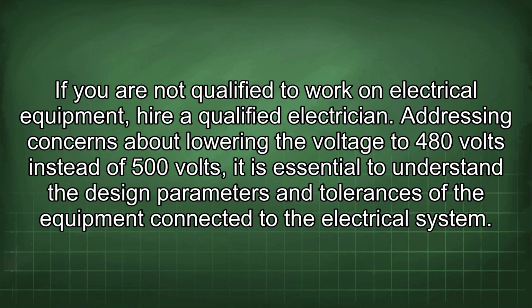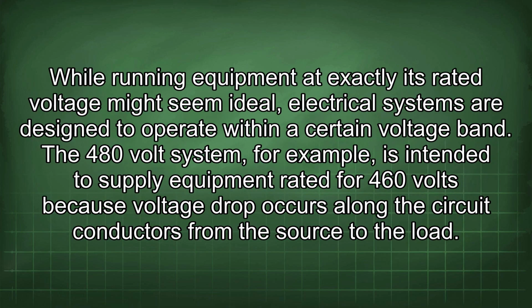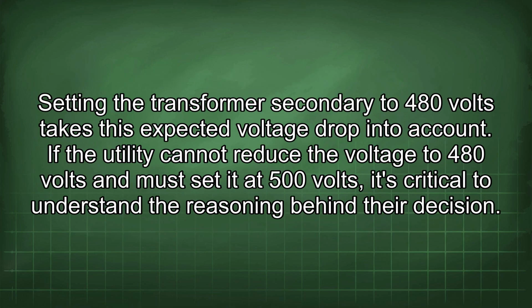Addressing concerns about lowering the voltage to 480 volts instead of 500 volts, it is essential to understand the design parameters and tolerances of the equipment connected to the electrical system. While running equipment at exactly its rated voltage might seem ideal, electrical systems are designed to operate within a certain voltage band. The 480-volt system, for example, is intended to supply equipment rated for 460 volts because voltage drop occurs along the circuit conductors from the source to the load. Setting the transformer secondary to 480 volts takes this expected voltage drop into account.